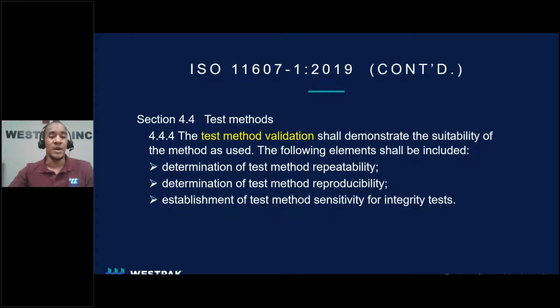The three key items that a validated test method must prove are that it must have a determination of test method repeatability, determination of test method reproducibility, and an establishment of test method sensitivity for integrity test, which can be considered the precision and bias.